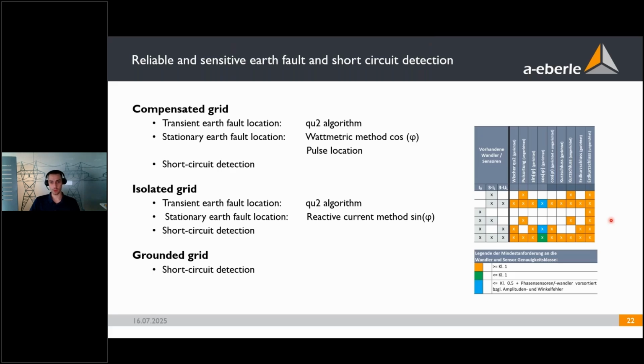And as you can see here, the last slide was just an example. The EOR-1DS does have a few more localization methods. So in the compensated grid, that would be the QU2 algorithm, the watt metric method, and the pulse location, as I said before, and of course, short circuit detection as well. In an isolated grid, you would have the QU2 algorithm as well, and also your reactive current method, the sine phi method.